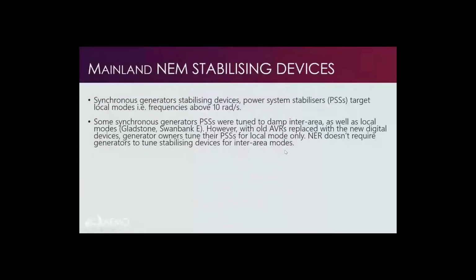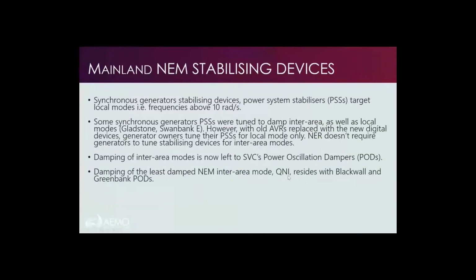Now the way stabilizers were tuned in the past was for the local mode and inter-area modes, but the National Electricity Rules don't require that. So usually what happens when old AVRs, automatic voltage regulators, are replaced with the new digital devices, owners would tune their PSSs for the local mode only. So damping of inter-area modes is now left to power oscillation dampers. And as I said, QNI, the weakest damped mode, resides with Blackwall and Greenbank PODs.